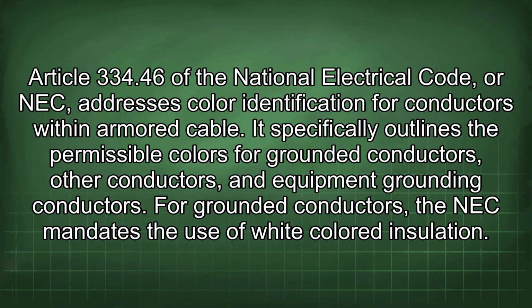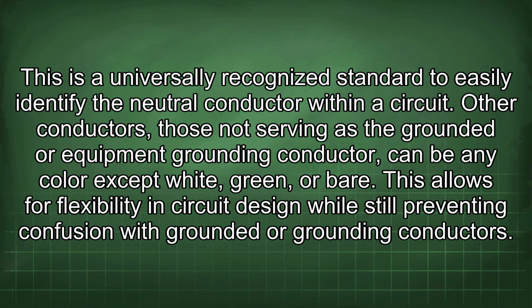Article 334.46 of the National Electrical Code, or NEC, addresses color identification for conductors within armored cable. It specifically outlines the permissible colors for grounded conductors, other conductors, and equipment grounding conductors. For grounded conductors, the NEC mandates the use of white-colored insulation. This is a universally recognized standard to easily identify the neutral conductor within a circuit.